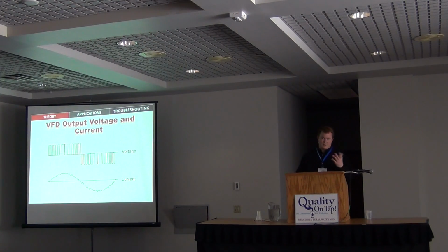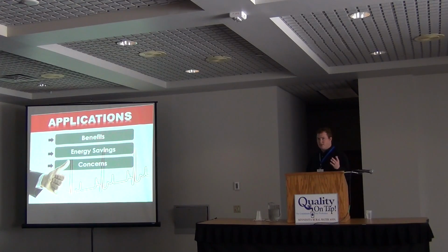Doesn't hurt your motor at all, assuming your motor is rated for VFD use. But the motor actually acts as a filter, and it filters these pulses into a somewhat smooth sine wave. And I say somewhat because all these little jagged edges here are something that, as an engineer, we have to deal with, or they might create problems on your system elsewhere. So that's kind of a summary of the theory of what a VFD is doing and why we're going to see some of these concerns and benefits from that.